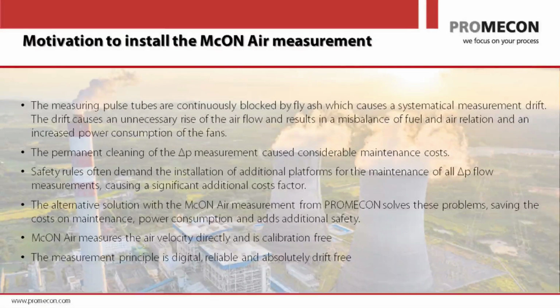Why are these high velocities important for you? Because very often people have an existing venturi, they have an existing airfoil, and the gaps of the venturi or the airfoil are very good measurement locations because they act as a perfect flow straightener. Right? So if you have an existing airfoil, existing venturi, to put our sensors in this location is really helpful. And then, of course, in these locations, you have very high air velocities. You can have air velocities up to 150, 160 feet per second.